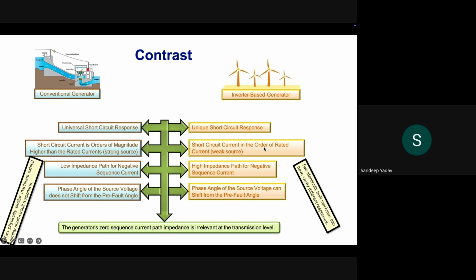However, in case of inverter-based resources, by virtue of using current-limited devices like semiconductors, usually in the form of IGBTs, their short circuit current is usually rated 1.2 or 1.3 per unit of the rated current. So there is a huge difference when it comes to the fault response of a conventional generator and an IBR generator.